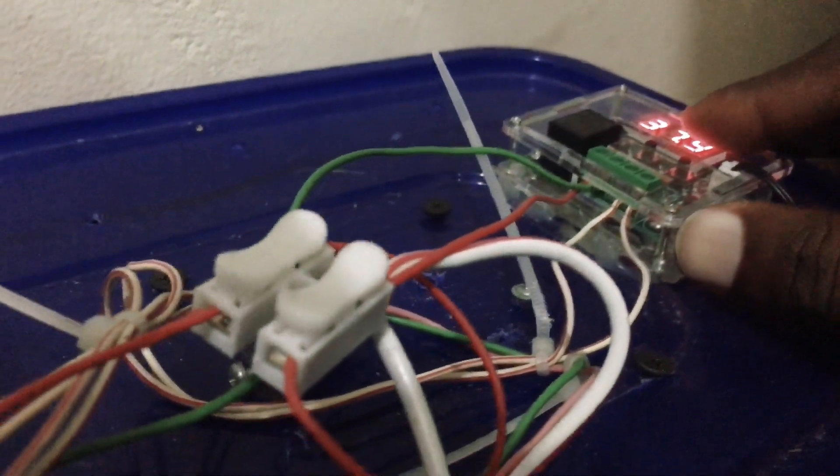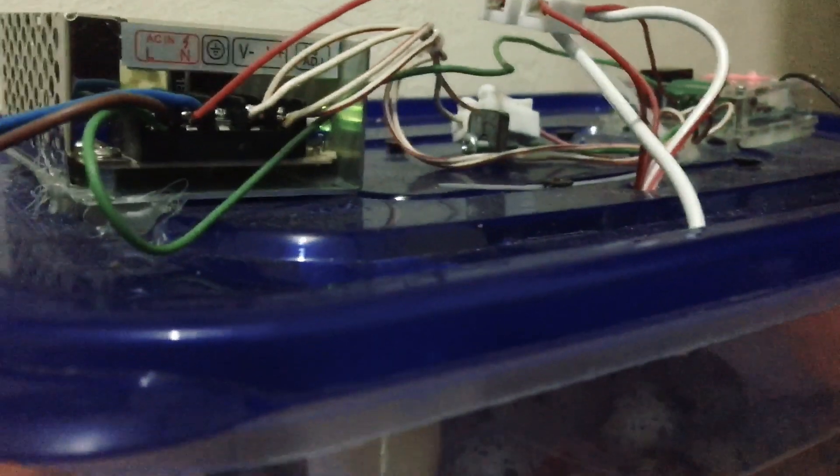And you can see I have two incubators here which I have done, and this controller is similar to this controller, so you shouldn't have a problem setting it. You can see they are corresponding to each other. So when this heater comes on, this one comes on. If this one goes off, this one goes off.